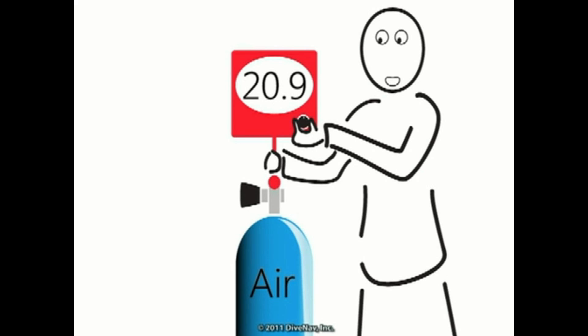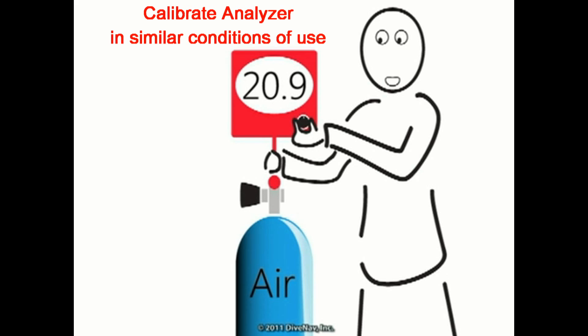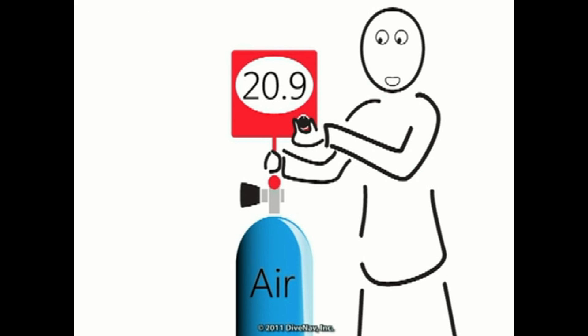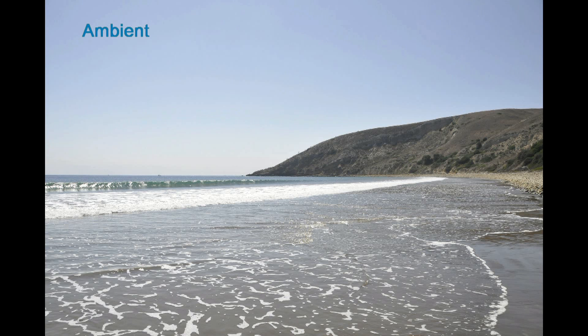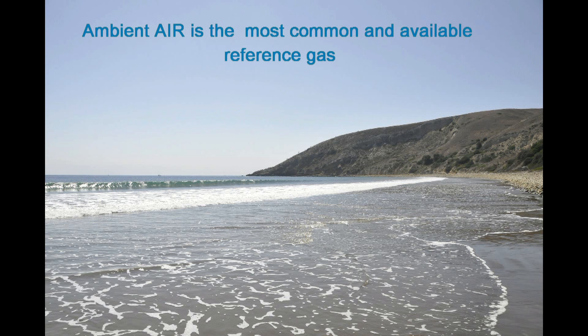Therefore, before you use an oxygen analyzer, it must be calibrated with a known reference gas used in similar conditions as the gas you want to analyze. The most common and available reference gas is the air we breathe — the simplest calibration is to use ambient air.